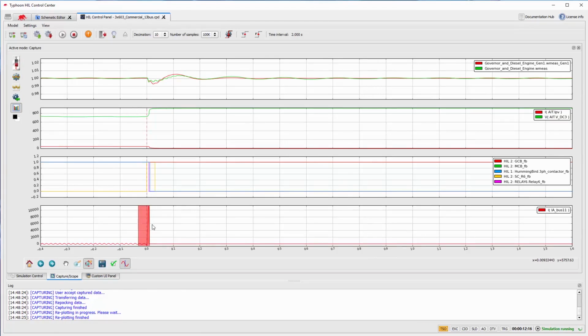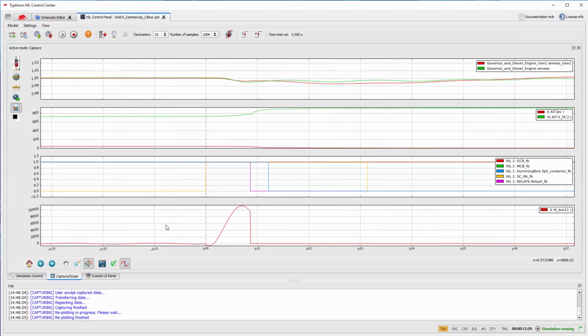This current is above the instant overcurrent limit IOC defined at the model initialization, and thus the relay is expected to trip instantaneously. Indeed, the relay 6 opened in less than 8 milliseconds after it crossed the IOC limit of 7 kiloamps. This time is less than 5 cycles, which is the maximum time required for a relay to open instantaneously.